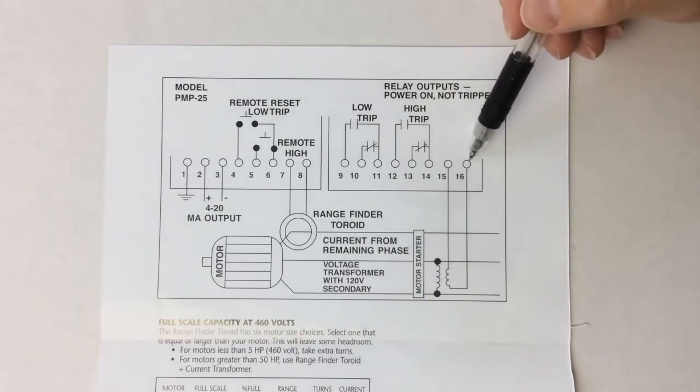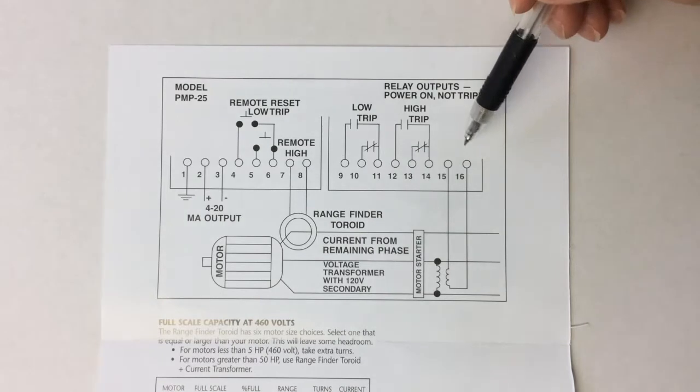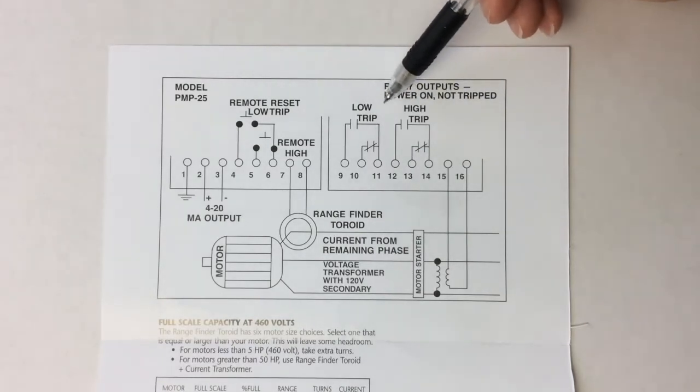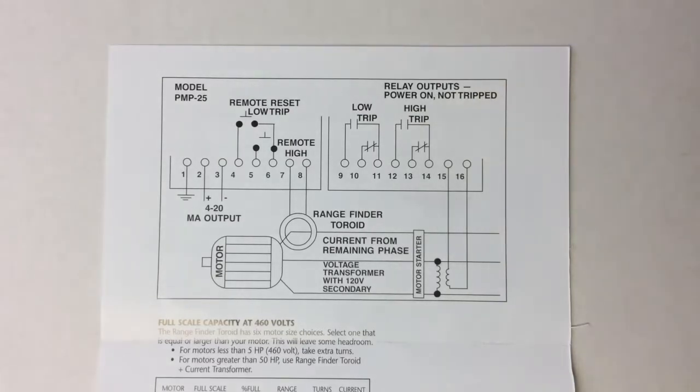When 120 volts is switched on to the PMP25, the output relays energize and the contacts move to the state shown. This is for fail-safe operation. If the 120 volts is lost or a failure occurs, the contacts will fail to the tripped condition, which is the shelf state of the relay contacts.